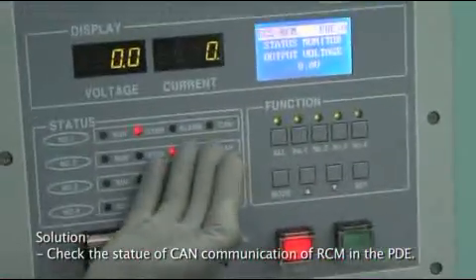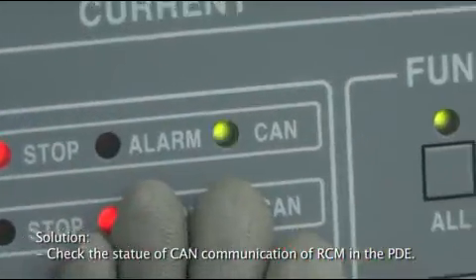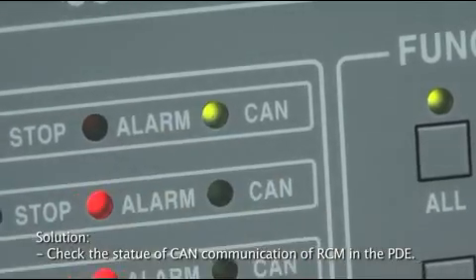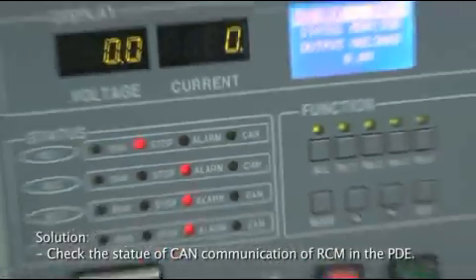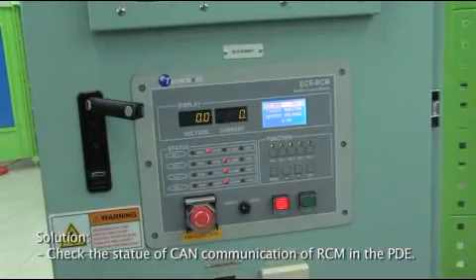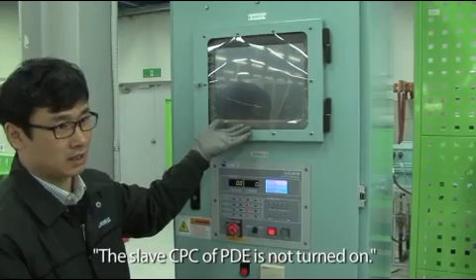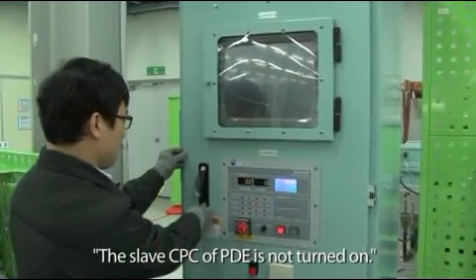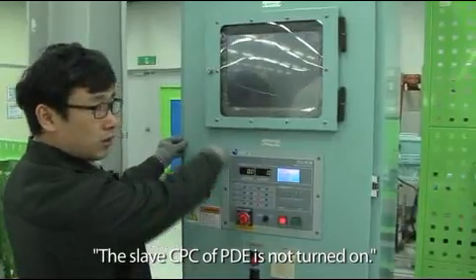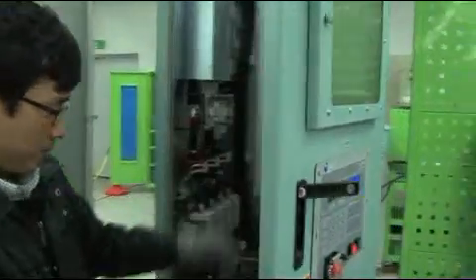In case of communication failure, check the connections of RCM connector and cables. If cables are loose, connect them tightly again. If the same problem persists, please contact the manufacturer. Problem. The slave CPC of PDE is not turned on. Solution.